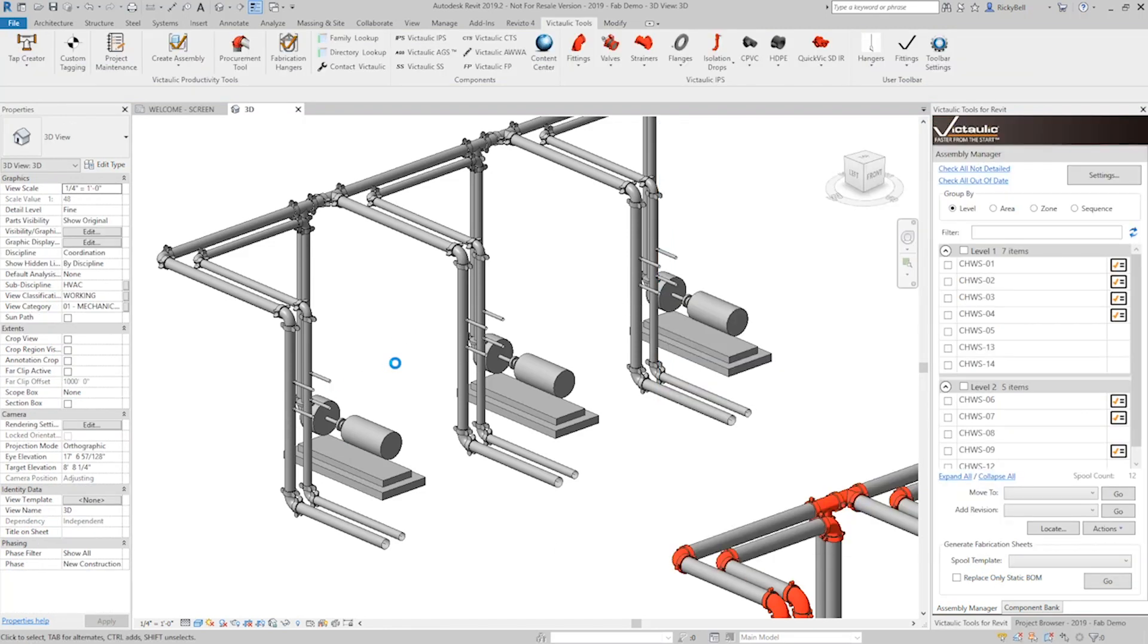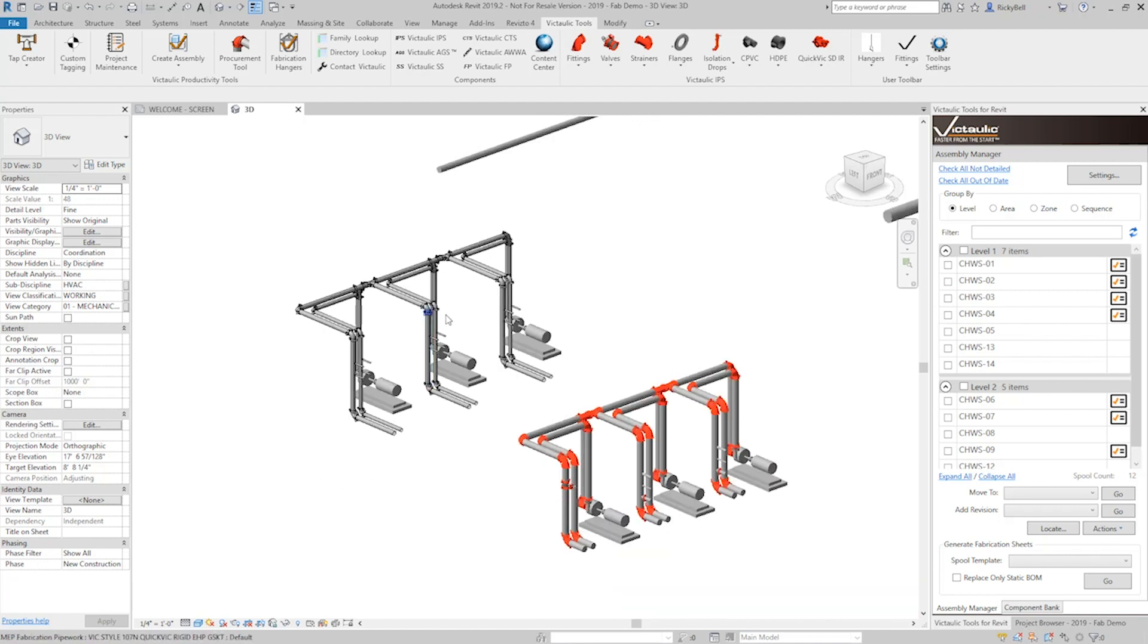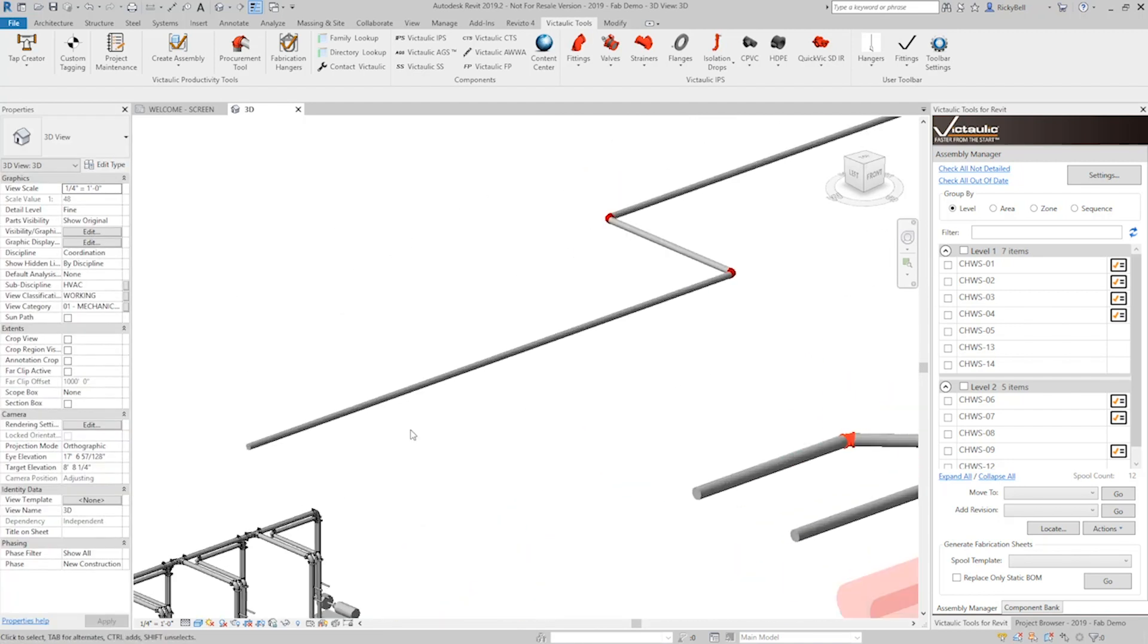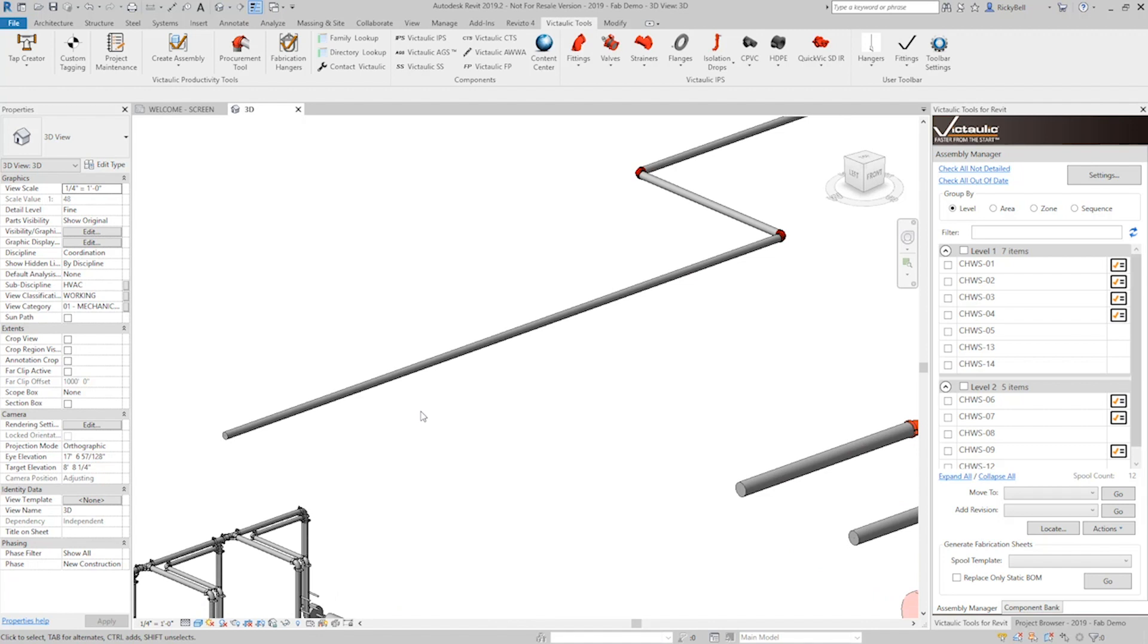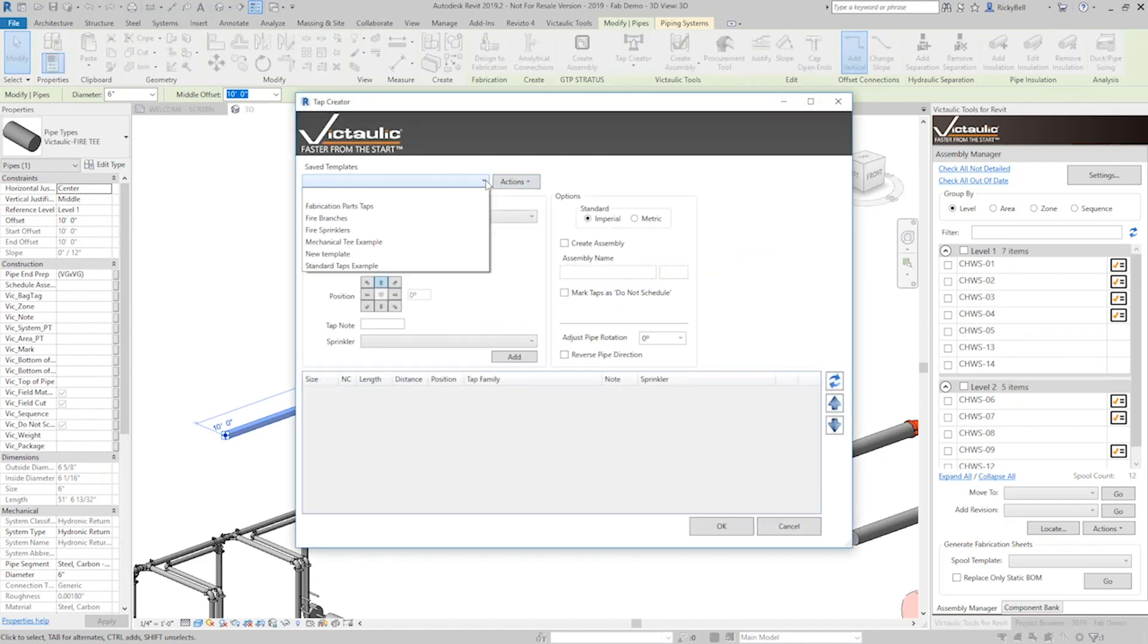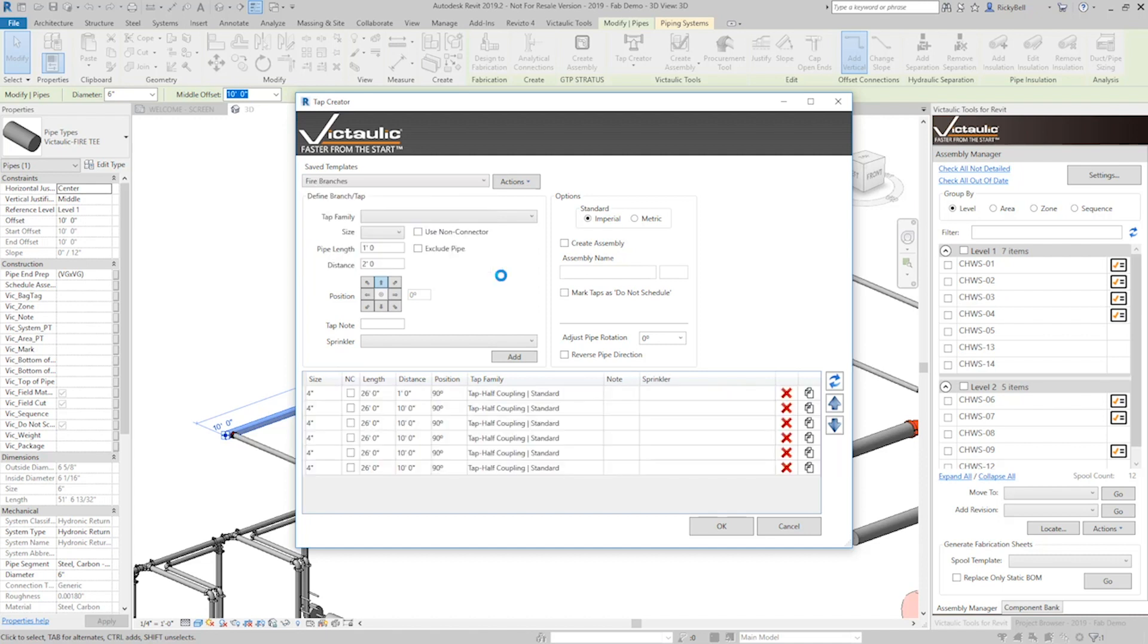So using some of these new features you can use your imagination as to where you could take this. I'm going to do a fire protection example because the tap creator has always been able to place sprinklers but using the tap creator you could place the branch lines as well. So here's what I came up with. I have this simple system right here which at the moment is just a big long stick of pipe, a main for fire protection. Now I want to draw some branches off of there. So just by clicking on the main, opening the tap creator, I've already set up a template called fire branches which is going to put in a branch every 10 feet.